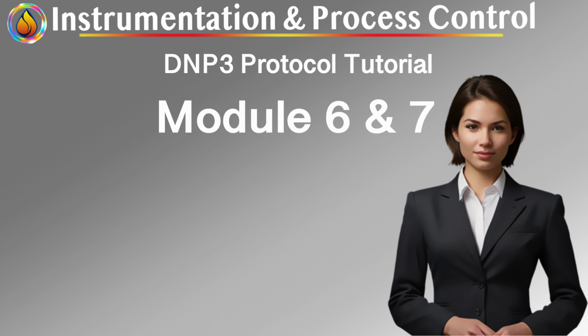6.6 Peer-to-peer communication. Role flexibility. DNP3 allows devices to dynamically assume master or outstation roles depending on context. In peer-to-peer configurations, a device may request data from another device. The same device may respond to requests from a third device. Role assignment is logical, not fixed. Use cases: distributed automation schemes, local protection coordination, redundant control paths. Peer-to-peer communication is carefully engineered to preserve determinism and avoid uncontrolled message exchanges.